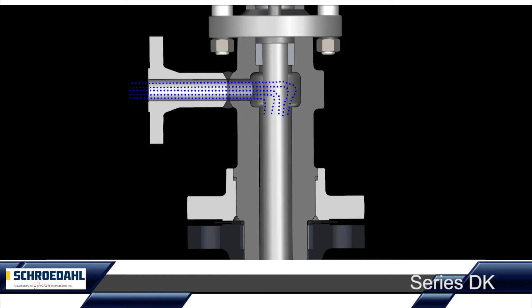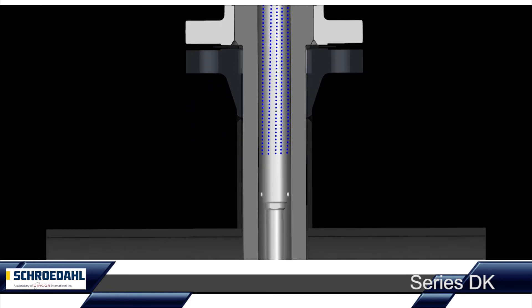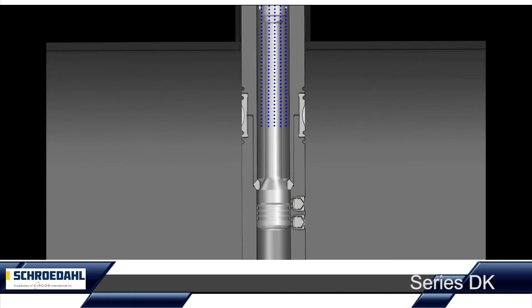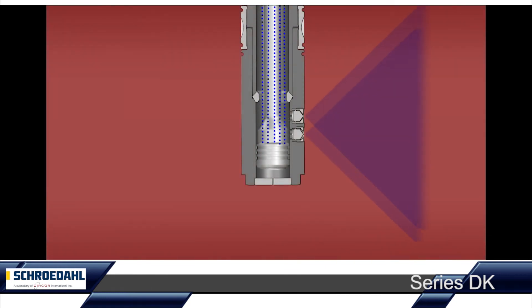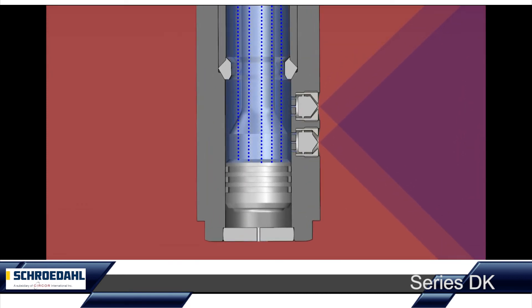The spray water flows down the shaft to the seat of the control piston. As long as the control piston is closed, the spray water does not flow to the nozzles. The steam to be cooled is detected via the temperature sensor and the appropriate amount of water is added via the desuperheater. The resulting steam temperature is compared with the target temperature and, according to the result, the steam cooler is controlled.